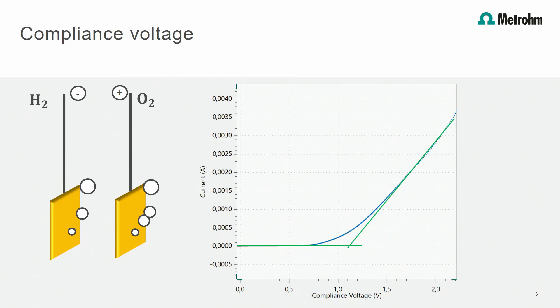The potential which is applied between the electrodes is called compliance voltage. To run electrolysis applications it is always necessary that the applied compliance voltage is higher than the decomposition voltage. Depending on the experiment this can be a quite high voltage and could push the potentiostat to its limits.